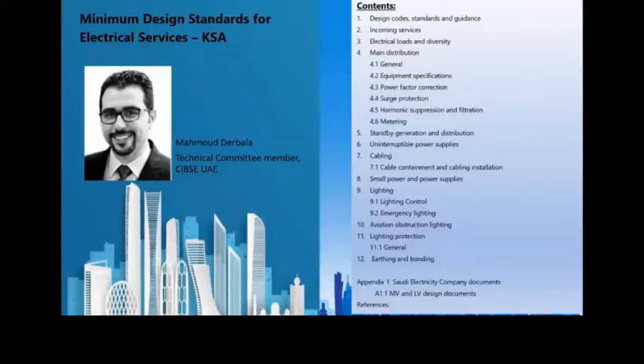In terms of load and diversity, which is Chapter 3, the electrical loads shall be assessed based on the individual site requirement, considering the local method of load assessment in accordance with the DPS, the Distribution Planning Standard regulation, for the volt ampere per meter square for each function or customer category, as Saudi Electric Company used to call it. So DPS01 provides the volt ampere per meter square for each category that needs to be considered in the load assessment stage.